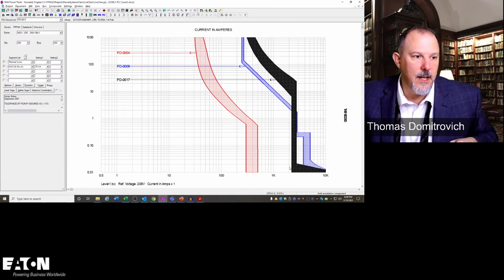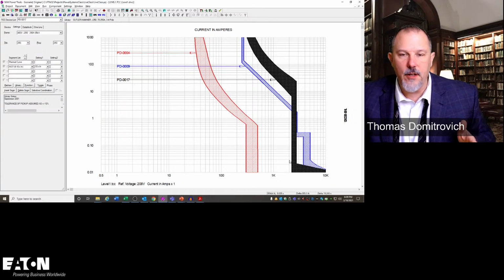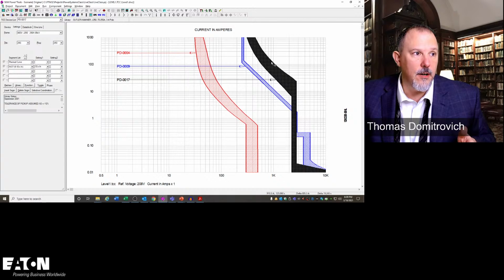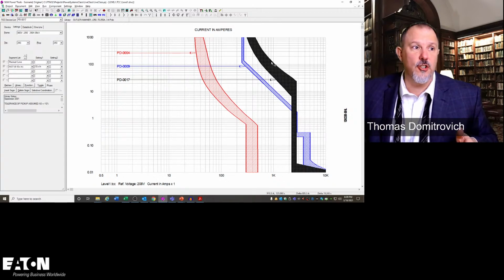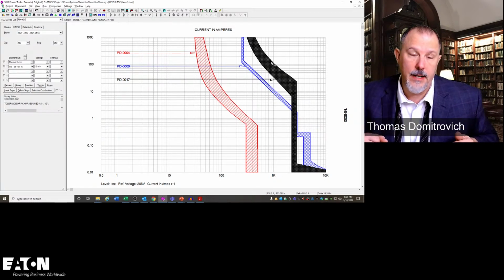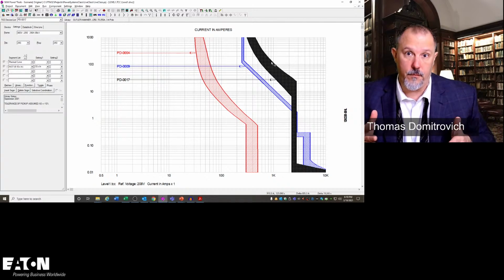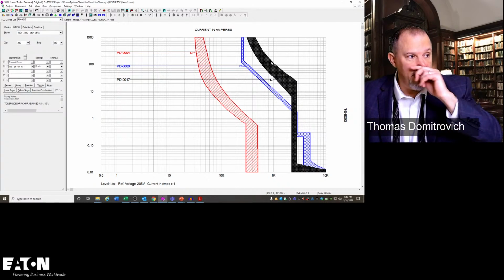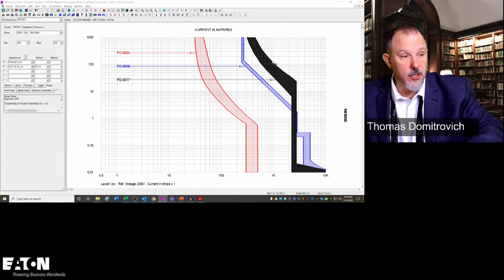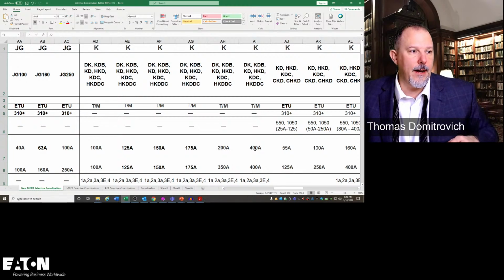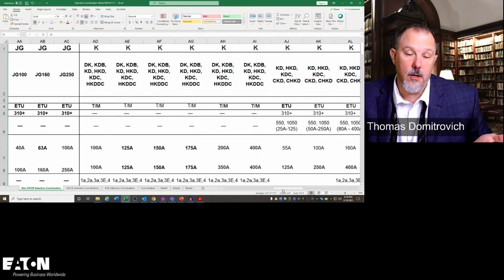If I pushed this instantaneous out as far, so that my bolted fault current value was less than the instantaneous pickup, where's my arcing fault current? It's down here. I'm way in the long time region. My incident energy went through the roof. It didn't just go up, it went through the roof. So with the thermomagnetic circuit breaker solution, when I start pushing it up, I don't think you're saving money in the long run. You may spend less money on the breaker, but you're going to spend more money on everything else.